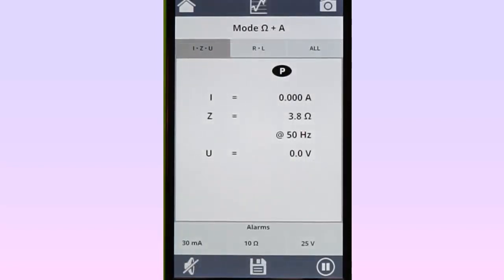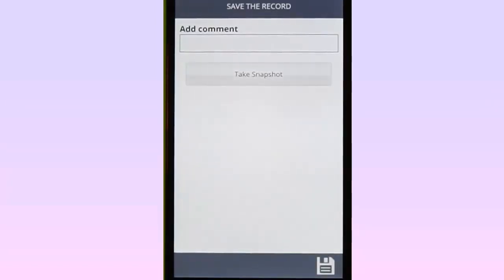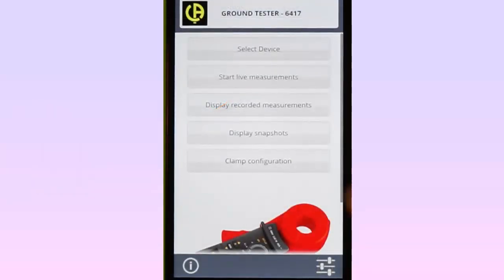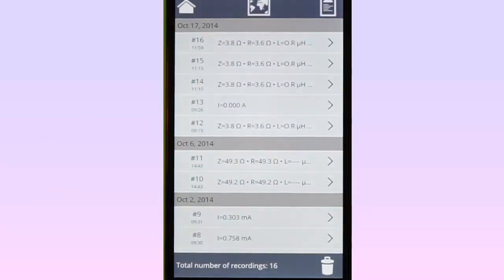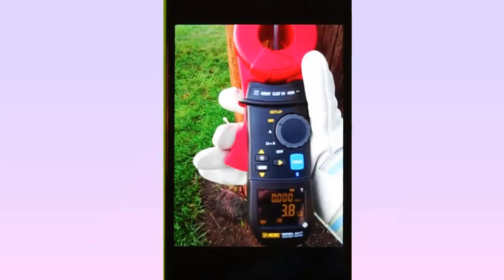When you create a non-graphical text record, you have the option of saving it as a quick data snapshot, or you can include more detail by adding a descriptive comment and a photograph. Display real-time data in text mode; at the bottom of the screen is the Save icon. A short tap saves the record as a screen capture snapshot. Touching the icon for several seconds displays the Save the Record screen, enabling you to add a comment and a photograph. After saving, it appears in the Display Recorded Measurements list. A thumbnail of the attached photo appears in the lower right corner.